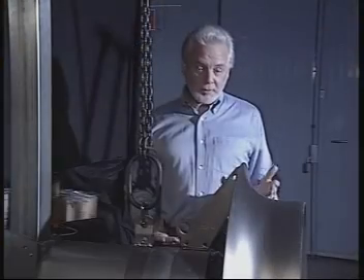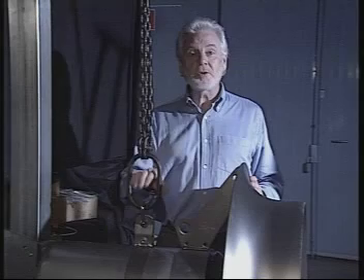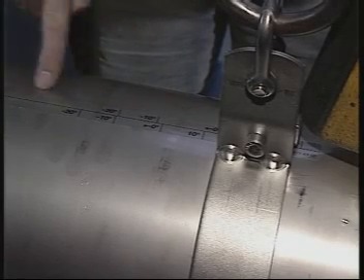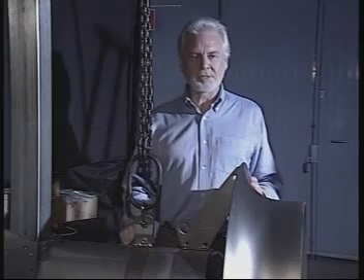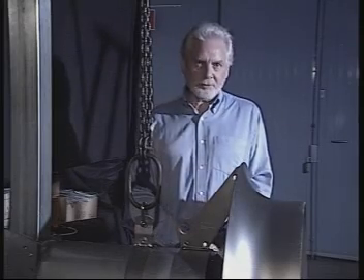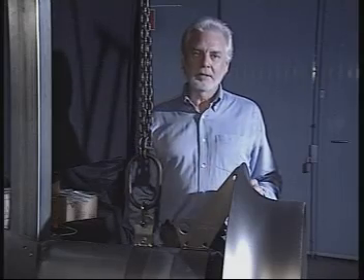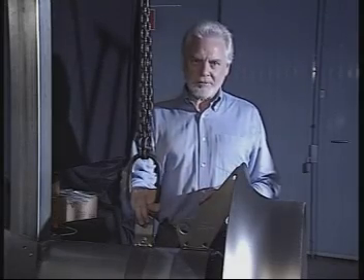The mixer should always be lifted from a point that represents its centre of gravity. A tape on the mixer indicates the position of the lifting handle for different angle positions. When installing the mixers, make sure that the cable cannot be pulled into the propeller. Always use the lifting device to lift the mixer, never the cable.